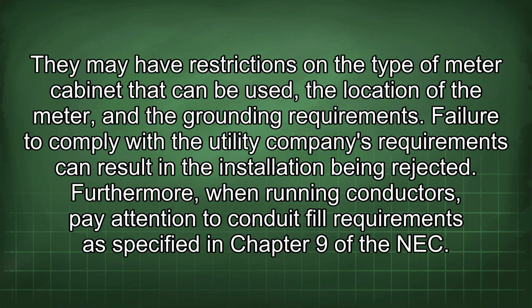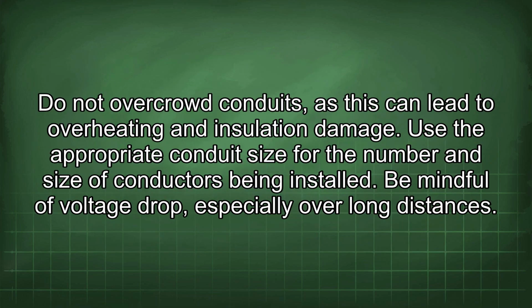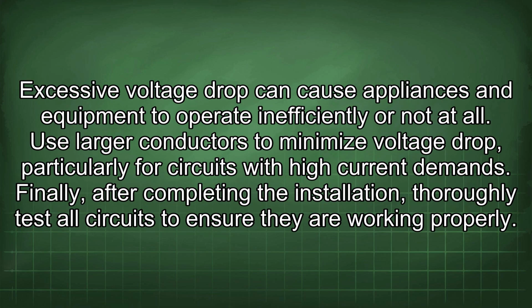Furthermore, when running conductors, pay attention to conduit fill requirements as specified in Chapter 9 of the NEC. Do not overcrowd conduits, as this can lead to overheating and insulation damage. Use the appropriate conduit size for the number and size of conductors being installed. Be mindful of voltage drop, especially over long distances. Excessive voltage drop can cause appliances and equipment to operate inefficiently or not at all. Use larger conductors to minimize voltage drop, particularly for circuits with high current demands.